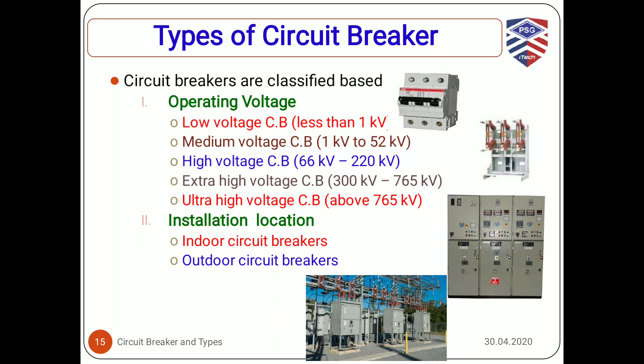Likewise, we can have medium voltage circuit breakers for voltages ranging from 1 kV to 52 kV. Meanwhile, a high voltage circuit breaker can be used for the voltage range 66 to 220 kV, and extra high voltage circuit breakers beyond that, that is 300 kV to 765 kV. Beyond 765 kV, we need to use ultra high voltage circuit breakers. And the next classification is based on the installation location where we are locating the circuit breakers. It is classified as indoor circuit breakers and outdoor circuit breakers. The third and fourth figures shown on the right hand side are the indoor and outdoor circuit breakers respectively.